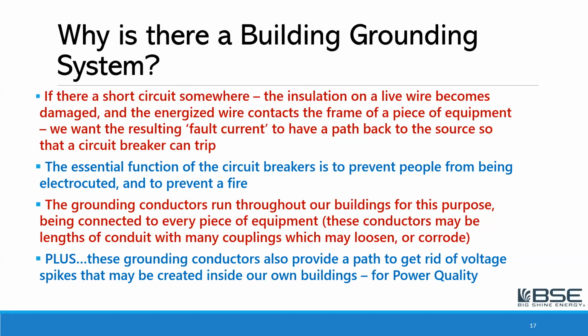It's good to review, why is there a building grounding system in the first place? The utility has to ground their system at the transformers outside our building. And that's to make sure that there's a stable reference for the voltage going into the building, and also to bleed off disturbances such as lightning strikes. But inside the building, there's an additional requirement. There's actually two requirements. One relates to safety and fire protection.